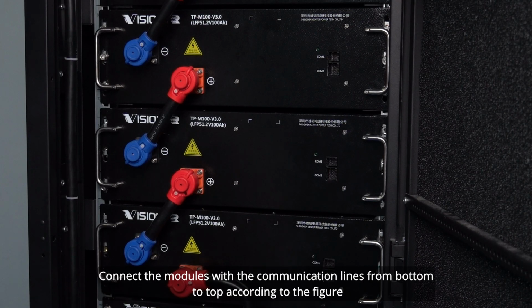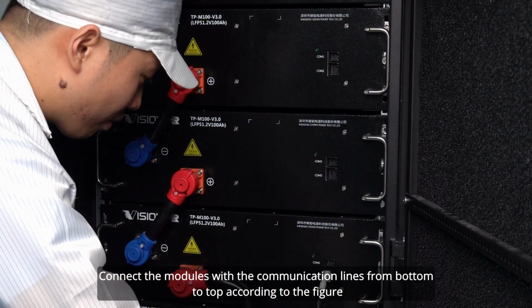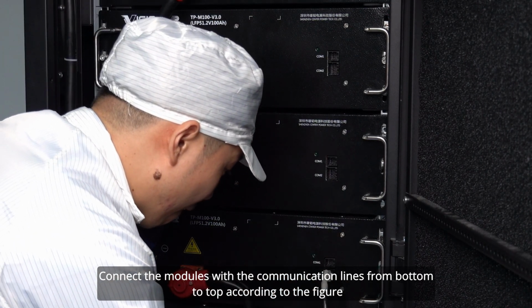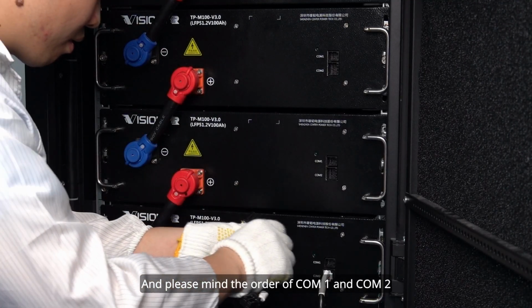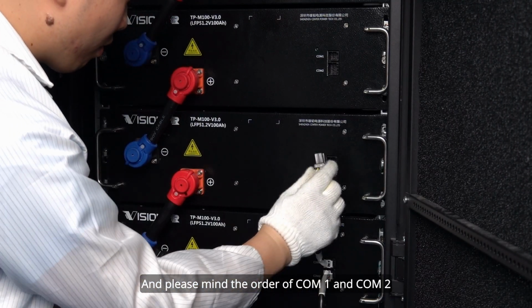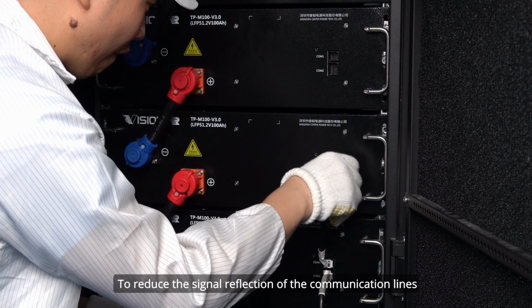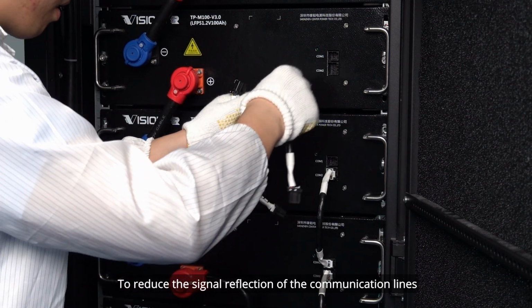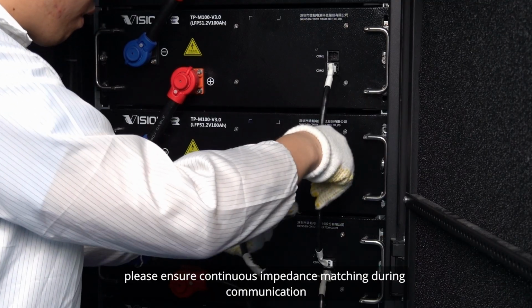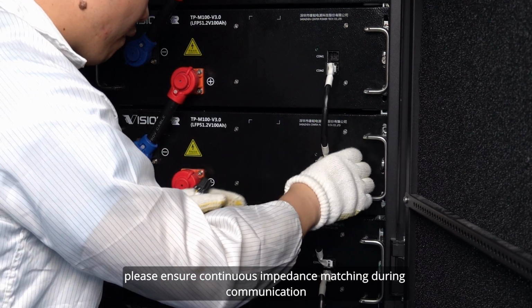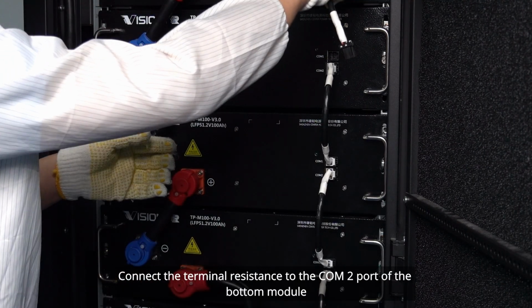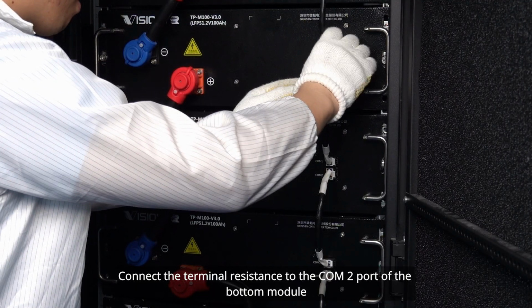Step 5. Communication connection. Connect the modules with the communication lines from bottom to top according to the figure. And please mind the order of COM 1 and COM 2. To reduce the signal reflection of the communication lines, please ensure continuous impedance matching during communication. Connect the terminal resistance to the COM 2 port of the bottom module.